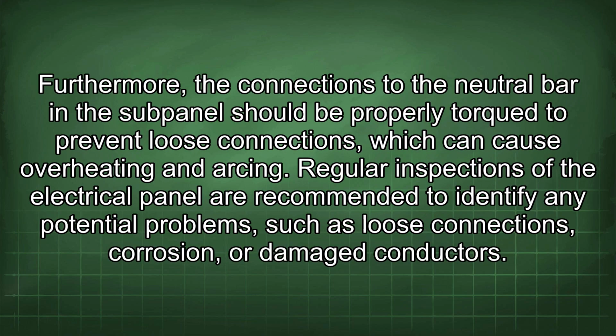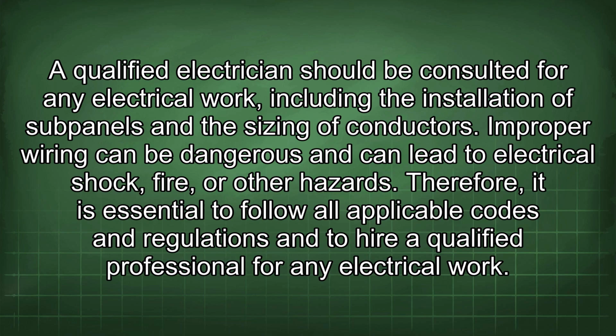It is important to consult these tables to ensure that the correct conductor size is used for the application. Furthermore, the connections to the neutral bar in the subpanel should be properly torqued to prevent loose connections, which can cause overheating and arcing. Regular inspections of the electrical panel are recommended to identify any potential problems such as loose connections, corrosion, or damaged conductors. A qualified electrician should be consulted for any electrical work, including the installation of subpanels and the sizing of conductors. Improper wiring can be dangerous and can lead to electrical shock, fire, or other hazards. Therefore, it is essential to follow all applicable codes and regulations and to hire a qualified professional for any electrical work.